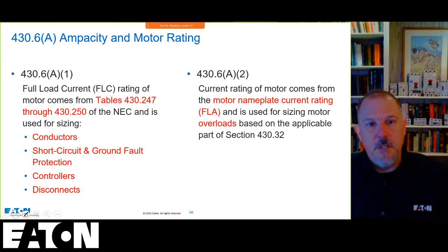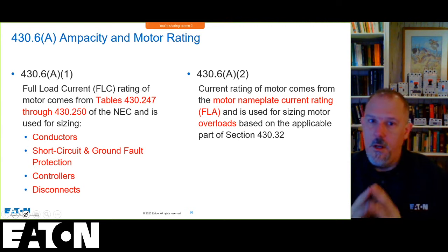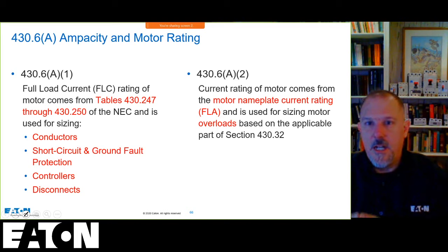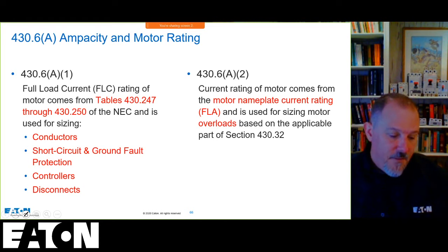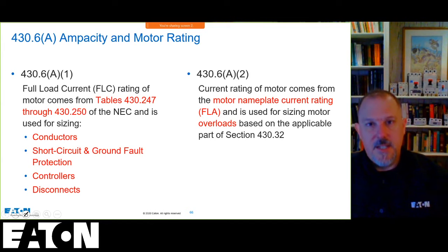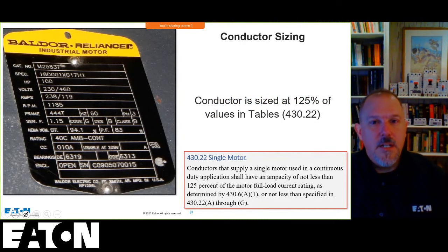I don't have to change my short circuit protection or my conductors, because I sized things for another motor that was the same horsepower, but a lower full load amps. And now I have another motor that's the same horsepower, but a higher full load amps. But I do the overloads based upon the nameplate ratings, because that's going to be more catered to the motor itself. And again, you can't forget about the exception in 430.6(A)(1), talking about the tables, and exception number two. So remember that from Mr. Fahey.